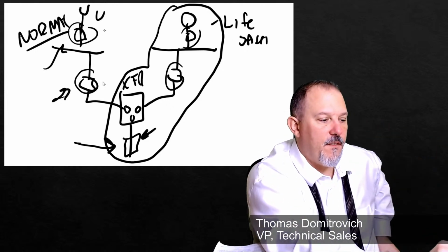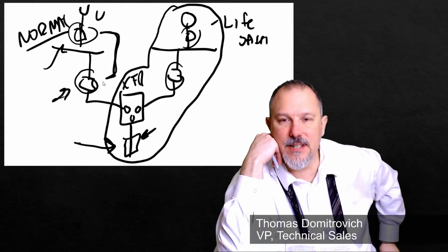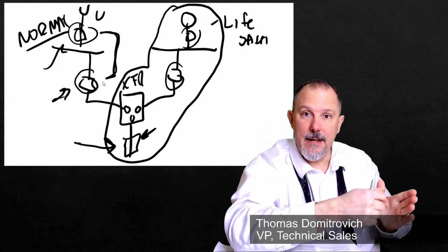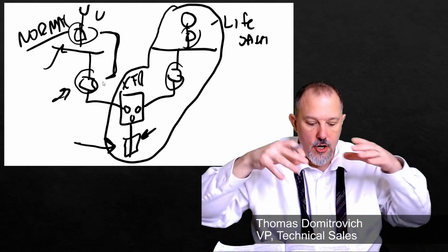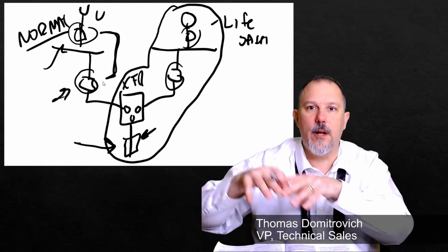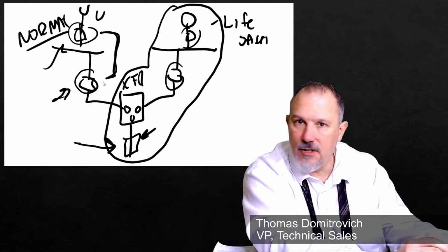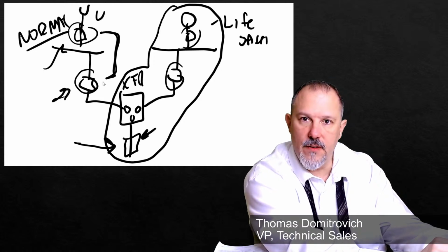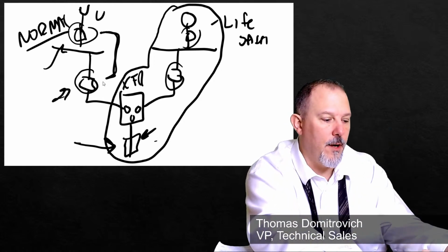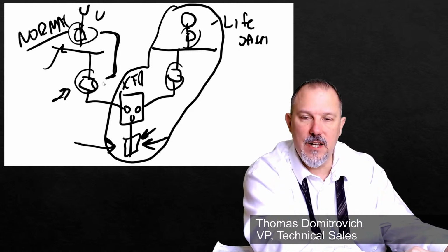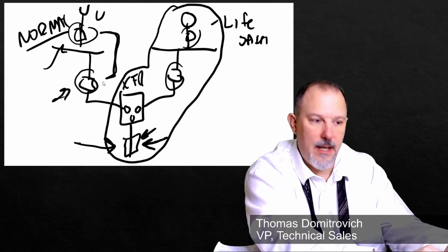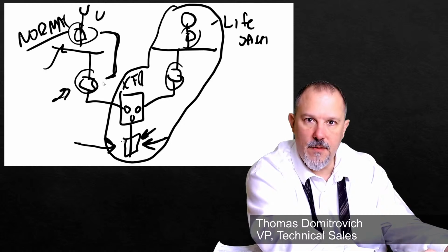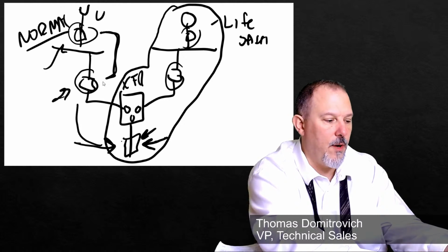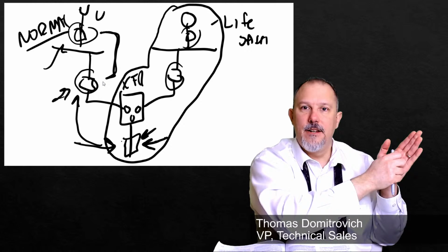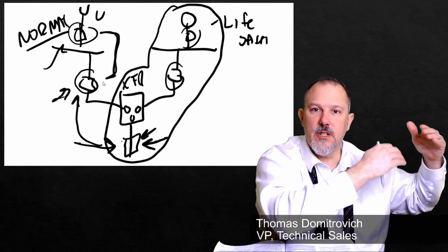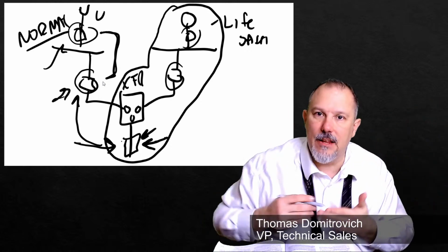But your feeder and your main on the normal side do not have to selectively coordinate with each other. Why? Because those two devices are not in the Article 700, 701, or 708 system. 700 does not have purview over those two devices. It does have purview over the devices that are in the life safety system. So the onus is that the device downstream of that transfer switch has to selectively coordinate with what's on the normal side. Not the devices on the normal side don't have to selectively coordinate with each other because they're not in the Article 700 system.